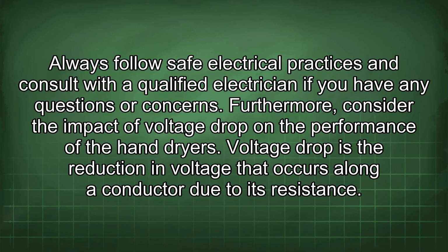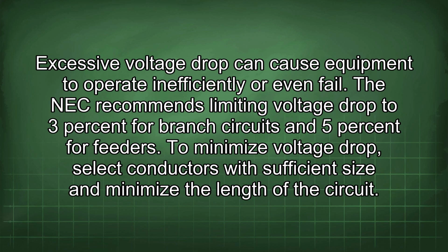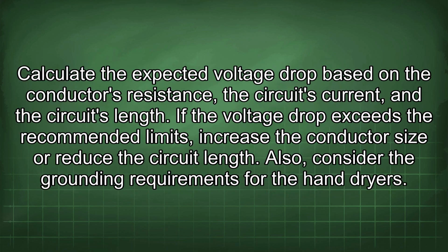Furthermore, consider the impact of voltage drop on the performance of the hand dryers. Voltage drop is the reduction in voltage that occurs along a conductor due to its resistance. Excessive voltage drop can cause equipment to operate inefficiently or even fail. The NEC recommends limiting voltage drop to 3% for branch circuits and 5% for feeders. To minimize voltage drop, select conductors with sufficient size and minimize the length of the circuit. Calculate the expected voltage drop based on the conductor's resistance, the circuit's current, and the circuit's length. If the voltage drop exceeds the recommended limits, increase the conductor size or reduce the circuit length.